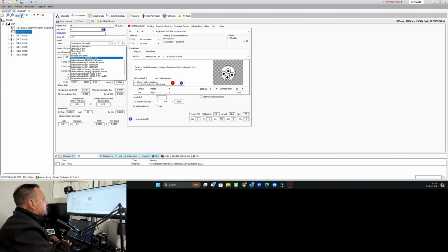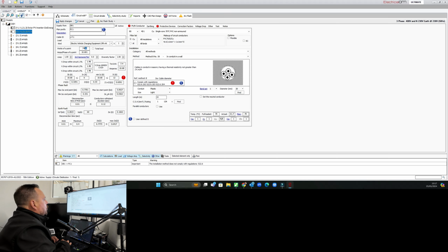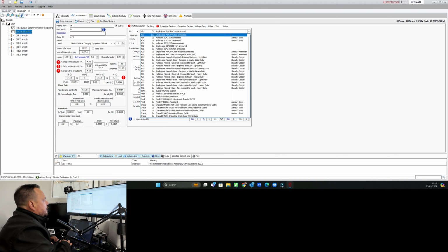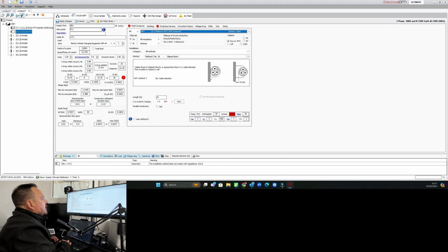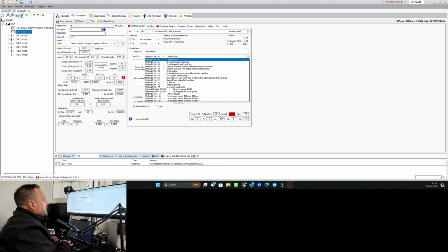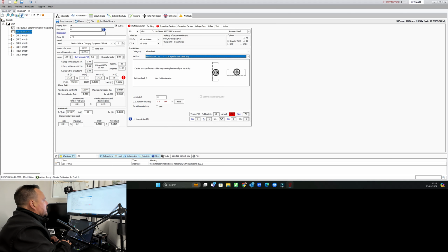So again, drop your little list down, we can see electric vehicle charging equipment. Watts, I'm going to put that as 22. This is where it gets a bit confusing because the last one was looking for it in kilowatts, and this is watts. So it's just watching out for that as you're developing your circuit layouts.